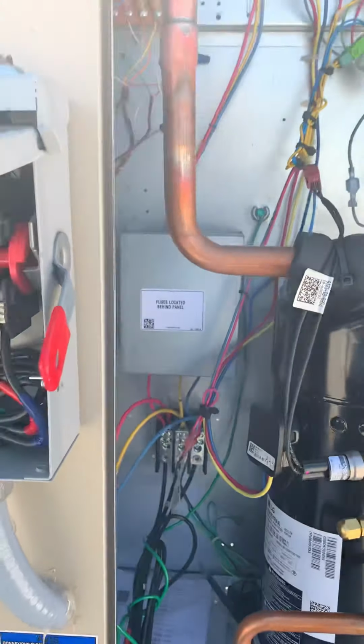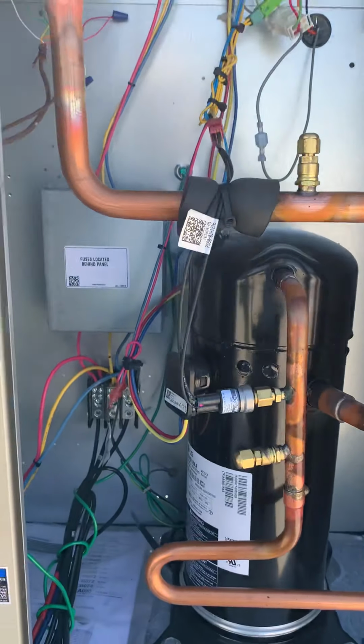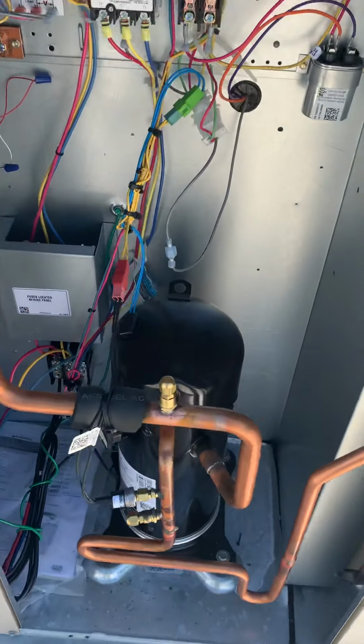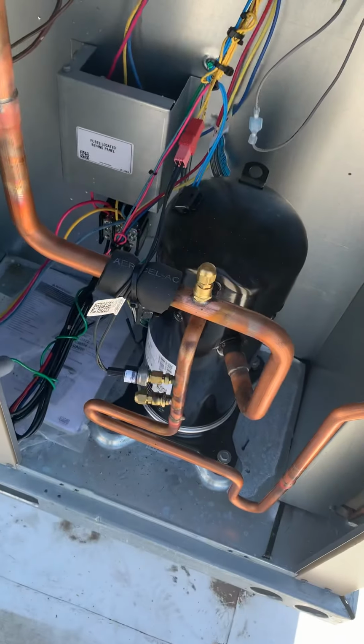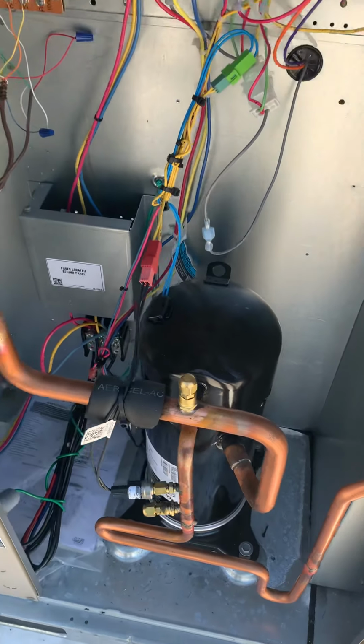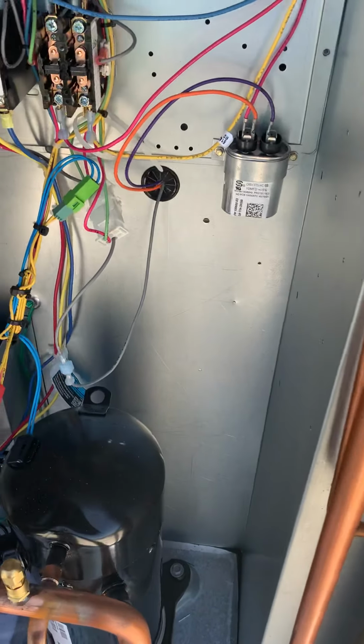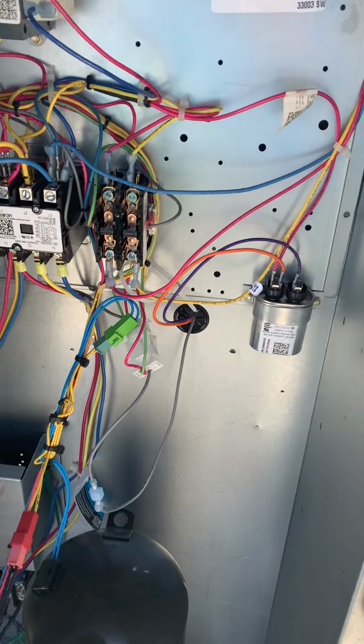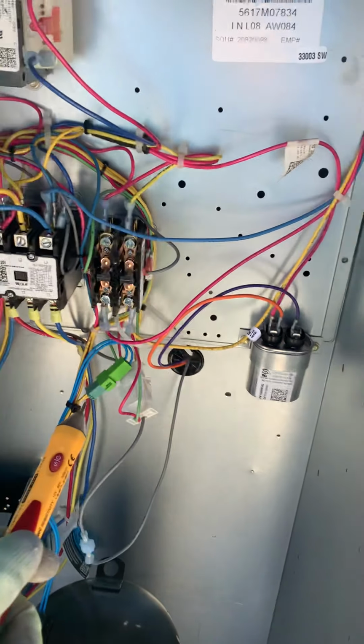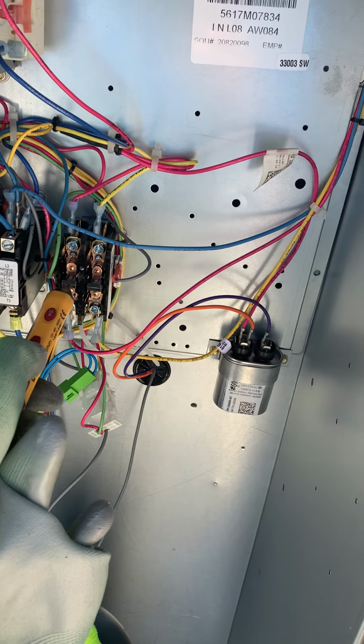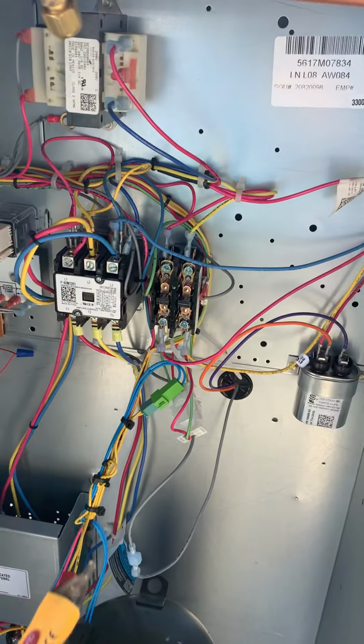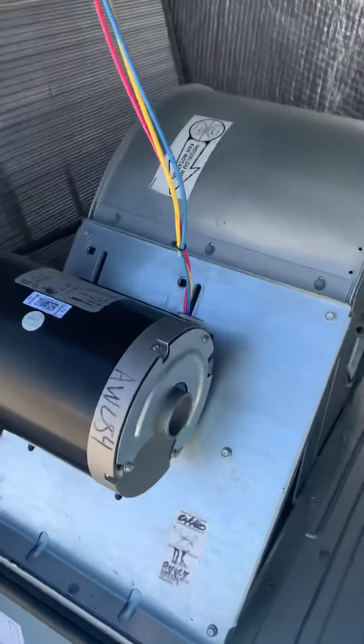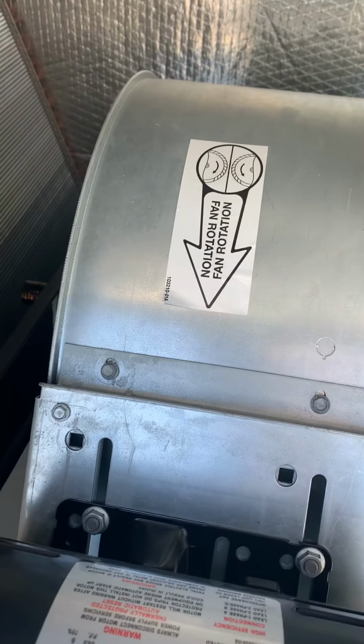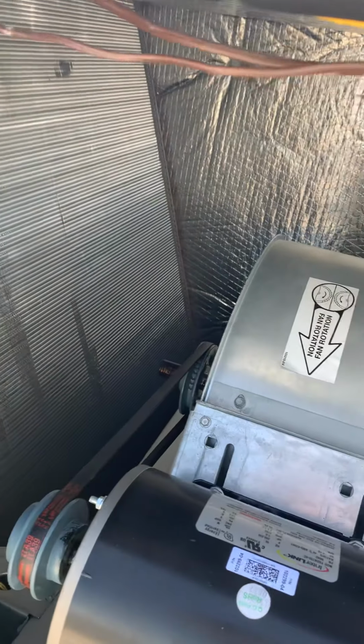Now on three-phase, a lot of times the units rotate backwards. So one thing you can do, I know this one's backwards, I gotta swap them. One of the easiest ways to check is by pushing the contactors, the wheel will rotate backwards. You can see there's an arrow there. It says the wheel's supposed to turn this way, towards me.